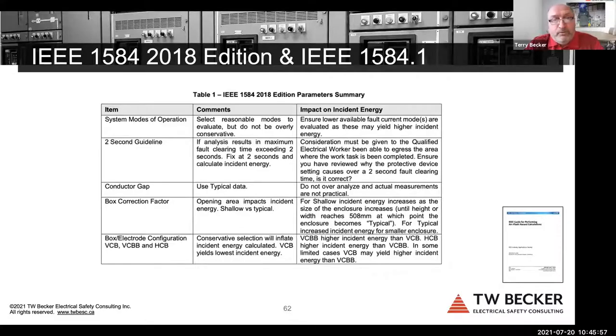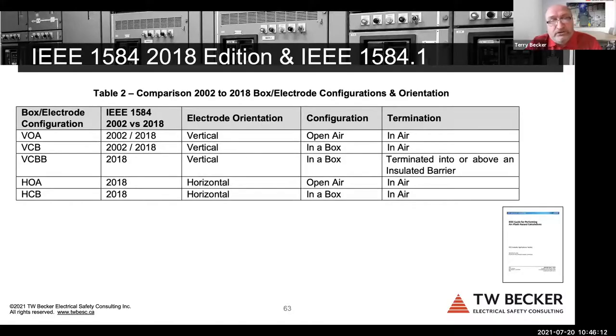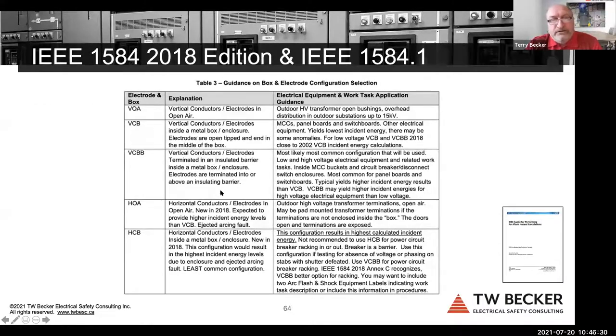And again, I've seen reports where there's been no substantiation of these parameters and the selection and the impact on incident energy. So again, that table is my interpretation of the impact. The biggest impact is the box electrode configuration and if HCB is selected. So cross-correlating the changes between the box electrode configurations again, and what was added was the VCBB and the HCB, right? And again, the new formulas, and the biggest impact in the new formulas is when HCB might be used. I've added and provided, and this might be another webinar, it probably is, where I'll go through this in more detail on my interpretation and my opinion, again, of the different parameters and the impacts they'll have and where they should be applied. In this case, the box electrode configuration.